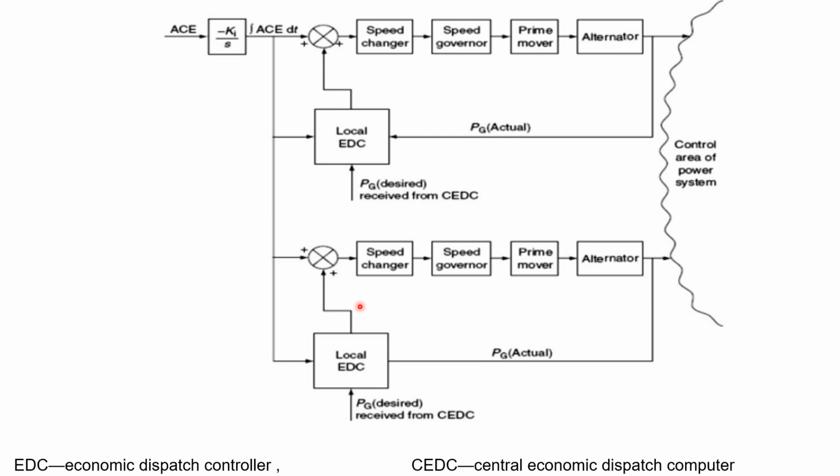So the system operates with economic dispatch error only for very short periods of time before it is readjusted. So through the operation of the integral controller, we can alter the position of the speed changer setting so that the generating stations produce outputs conforming to whatever the demand requires.